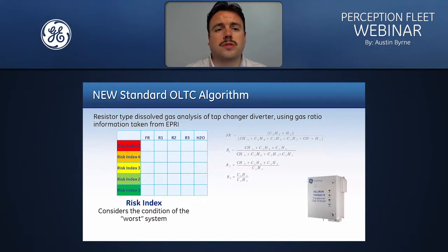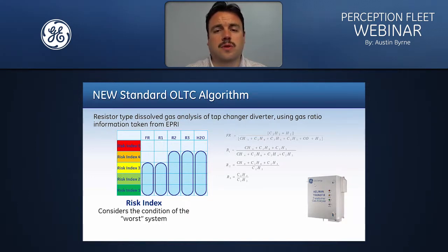Another new algorithm we've introduced is our standard OLTC algorithm, and that looks at resistor type dissolved gas analysis of the tap changer diverter using gas ratios taken from EPRI. You can see the ratios on the right hand side of the screen, and the table on the left hand side shows the effect on the risk index for that asset. For FR and R1, the highest risk index that the asset can achieve is a risk index of 3, whereas for R2, R3 and moisture, it can achieve a risk index of 4.